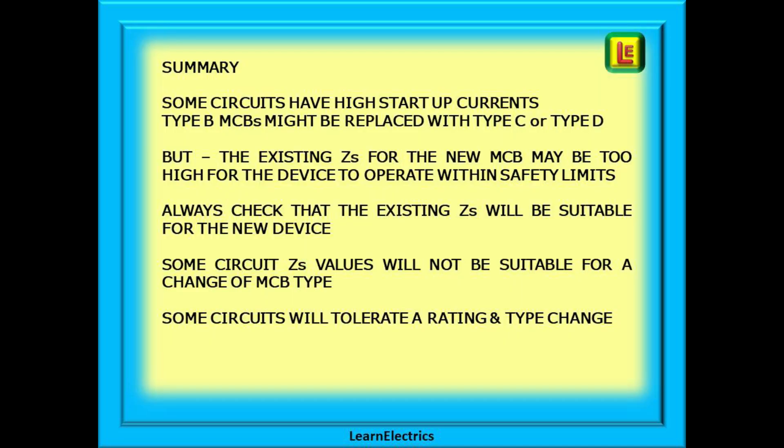A quick summary. Some circuits have high startup currents. Type B MCBs might be replaced with type C or type D. But the existing ZS for the new MCB may be too high for the device to operate within safety limits. Always check that the existing ZS will be suitable for the new device. Some circuits have ZS values that will not be suitable for a change of MCB type. And for other circuits a change of MCB rating and type is the way forward.